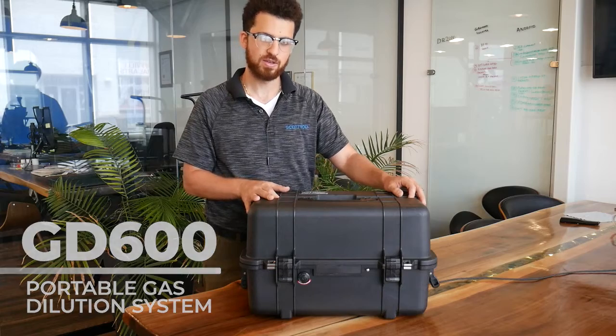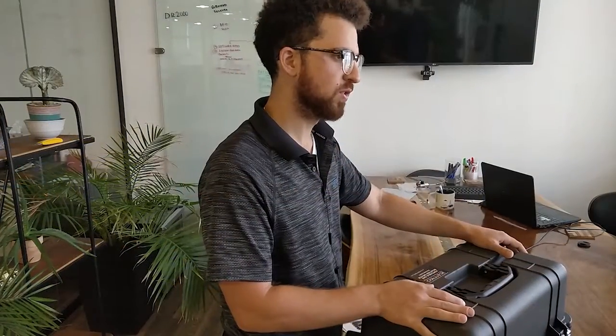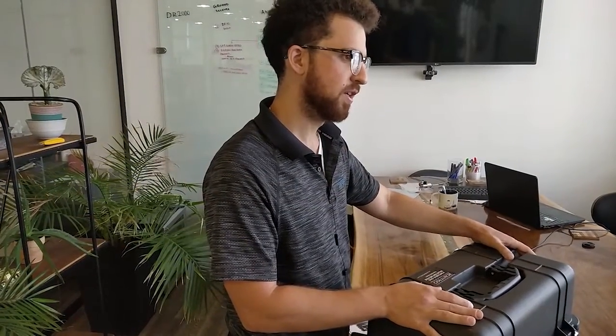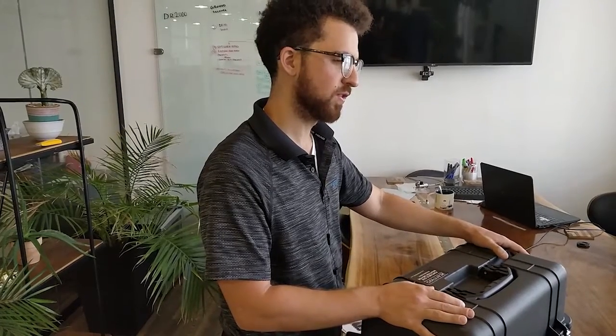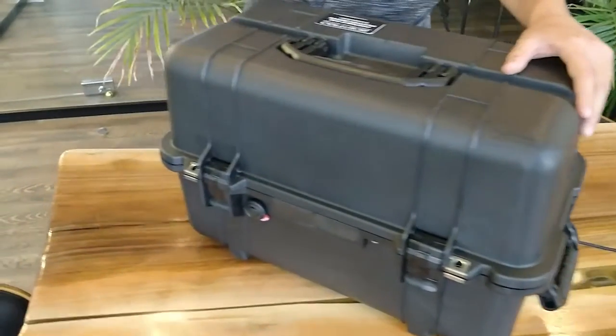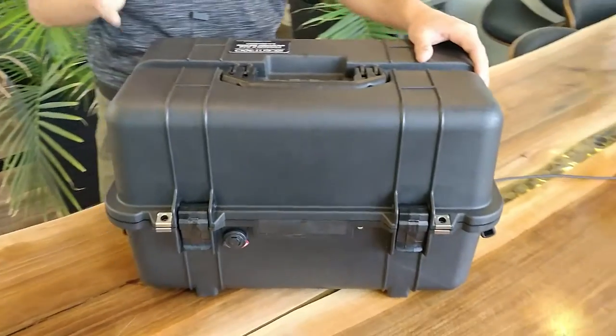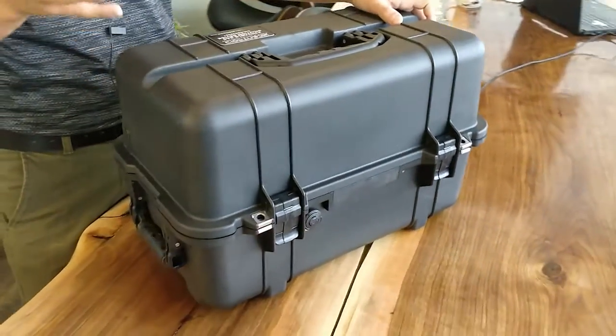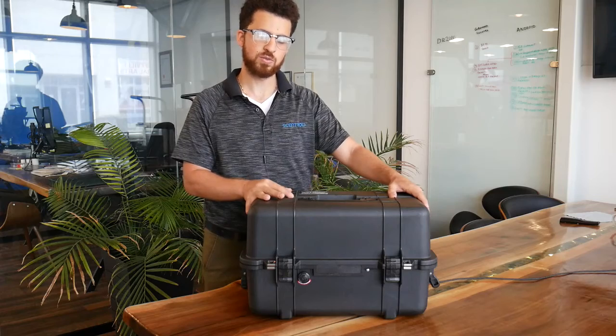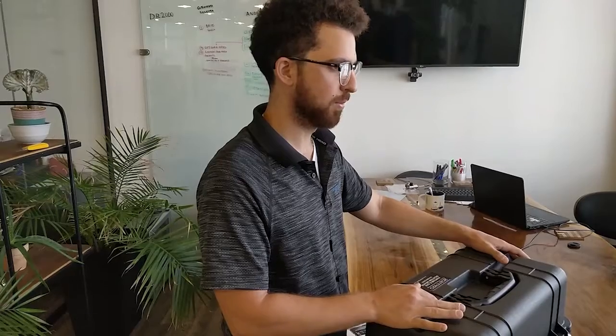The GD600 dilutes a reference gas into smaller known concentrations. This is the perfect companion for in-field calibration, as it has a two-stage scrubber used for generating its own zero air. It has a 6,000 milliamp battery, so you don't need to have it plugged in. And all you really need is just the calibration gas, and you're ready to go.